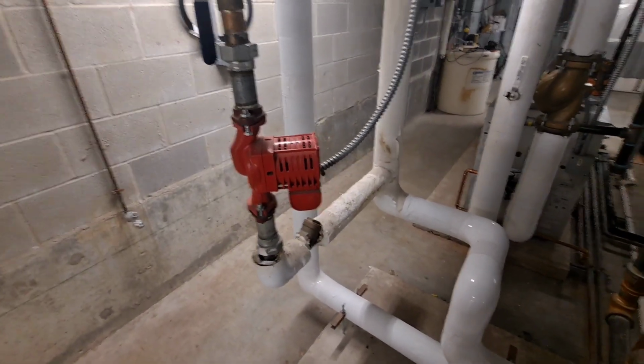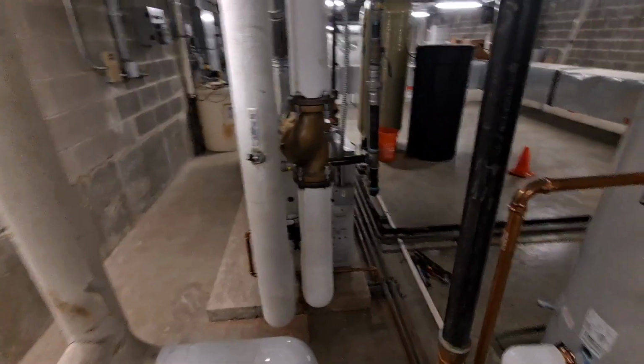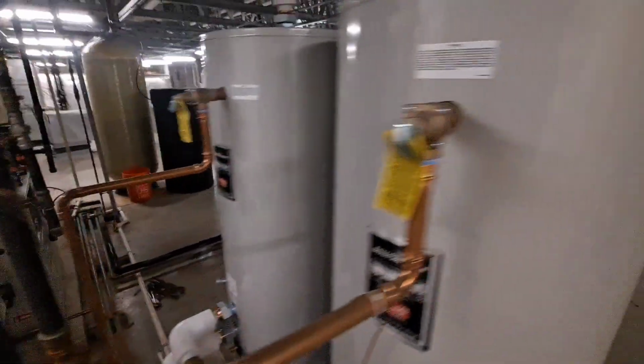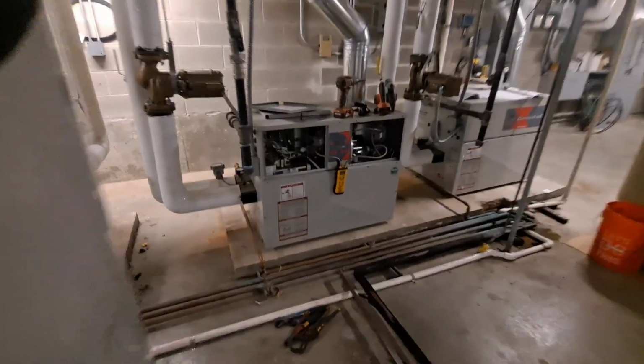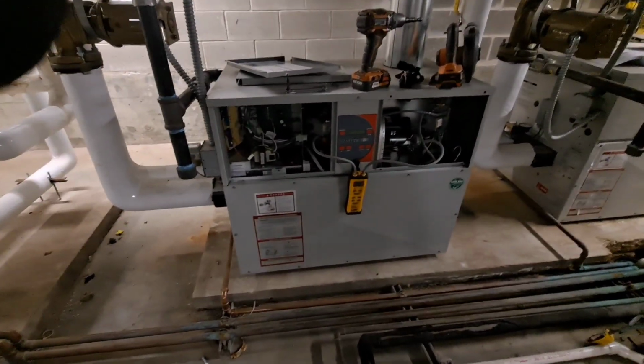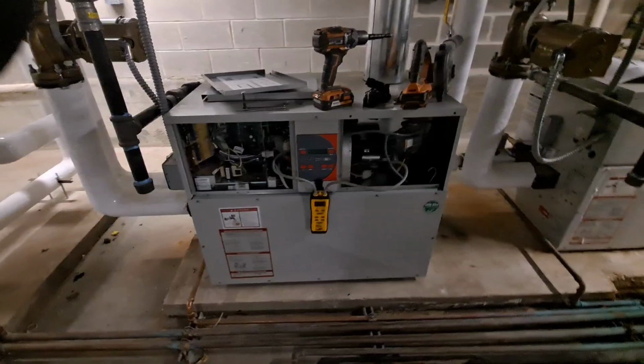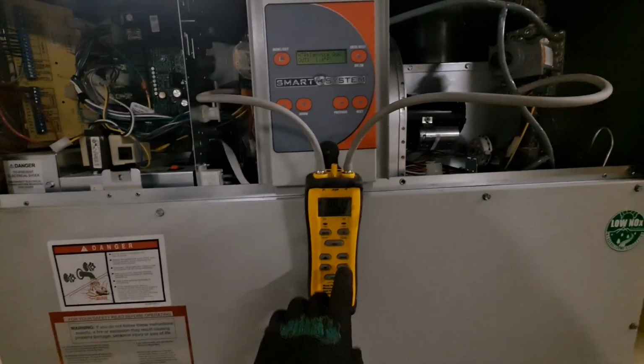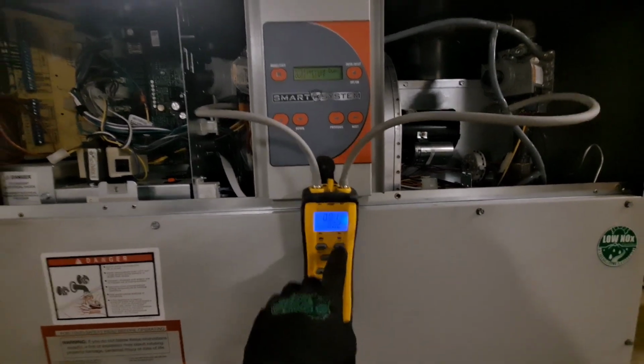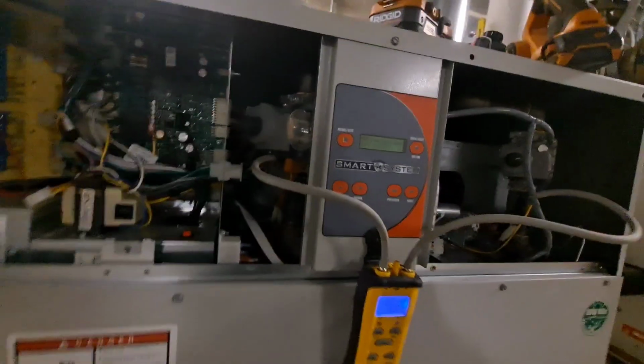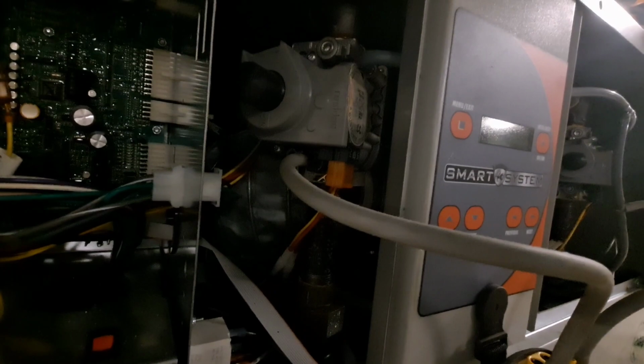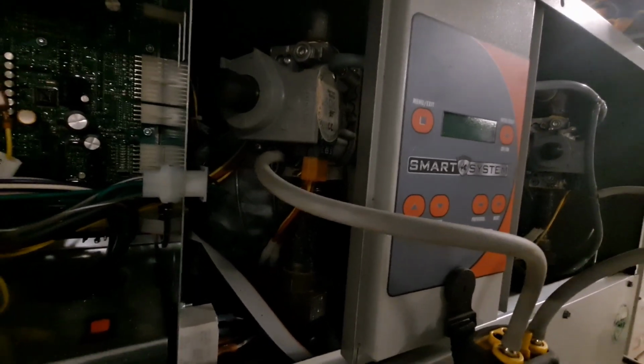system pump right here, boiler pump, and right now I just pulled and cleaned the heat exchanger, which I have a previous video on it, but this video is about setting and checking manifold gas pressure. So what you do is you connect like you normally would on the bottom of a gas valve, but then you also connect in over here.